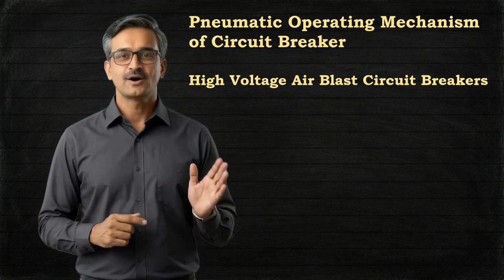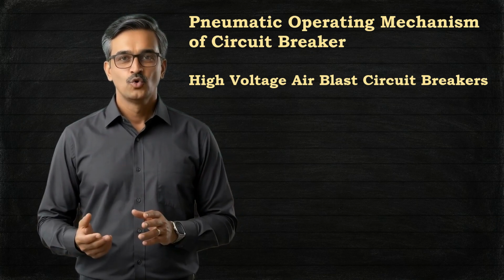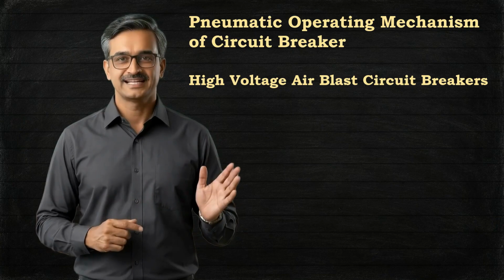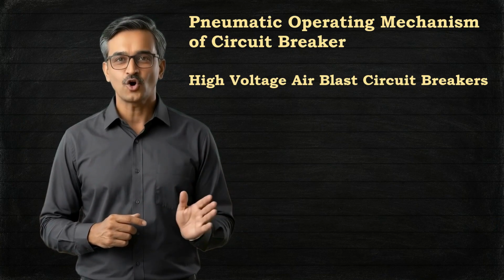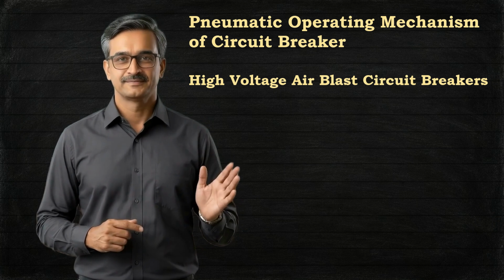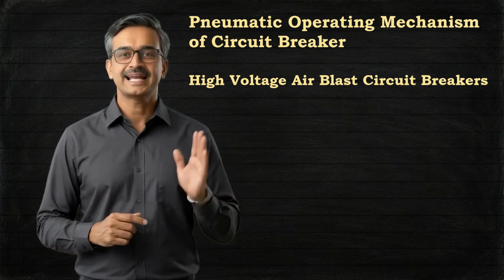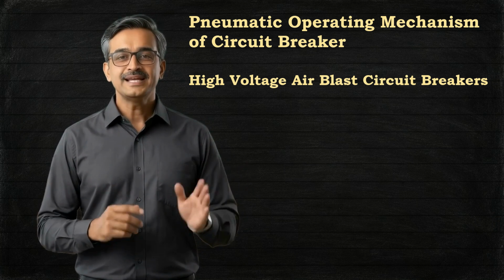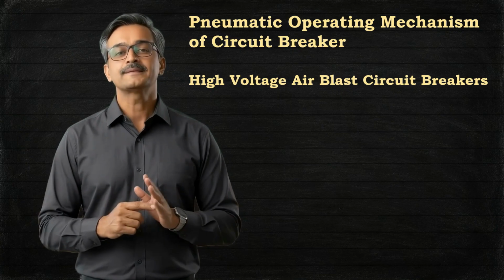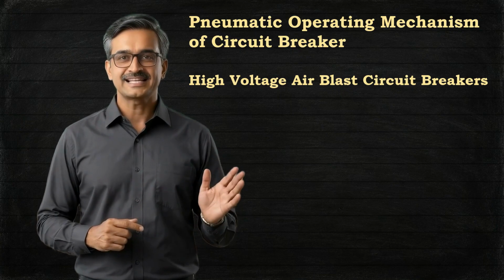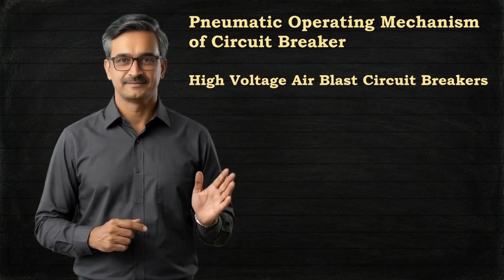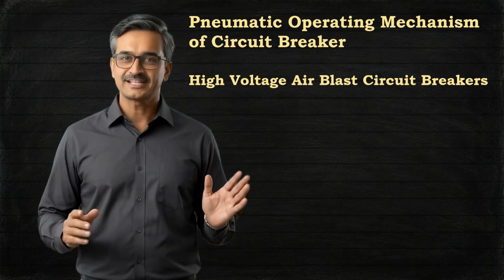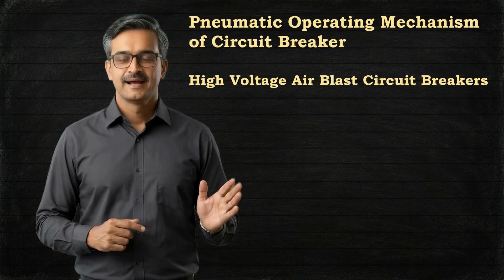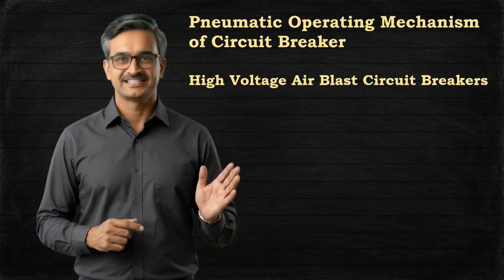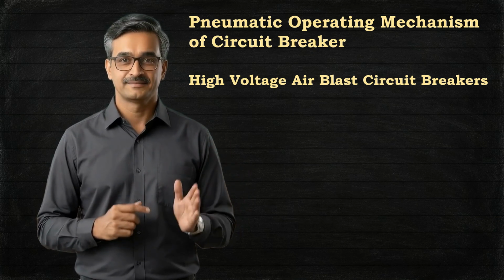However, for the sake of our study, we may discuss the overall idea of the pneumatic mechanism for the closing and opening operations of a circuit breaker. Here, atmospheric air is compressed with the help of an air compressor through a filter. This compressed air is then supplied to a pneumatic cylinder. The piston inside the pneumatic cylinder is pushed back due to the expansion of the compressed air inside the cylinder.